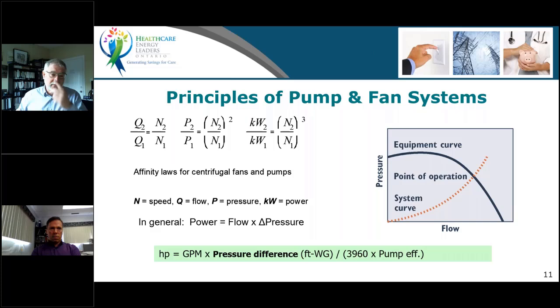Now, for changes in speed of the pump, we know that the flow varies according to the speed. That is, if you want double the flow, in simple terms, you double the speed of the pump itself, spin it faster. Now, if you want double the pressure, you have to look at the relationship: if you double the speed, you actually generate 4 times the pressure difference. So if we have a pressure requirement, we have to look at the second relationship. But the consequence of all of this is that for a change in speed or flow, we end up with a cubic relationship between the old and the new speed and the old and the new power. That is, if we want to double the flow, we need 8 times as much power for a given system to get that same flow through it.